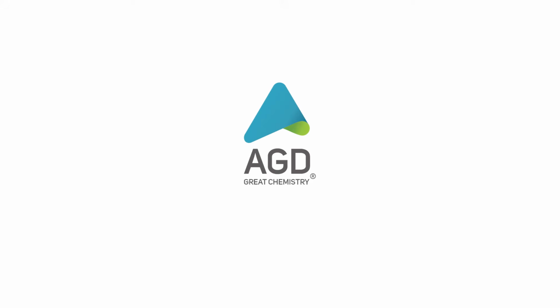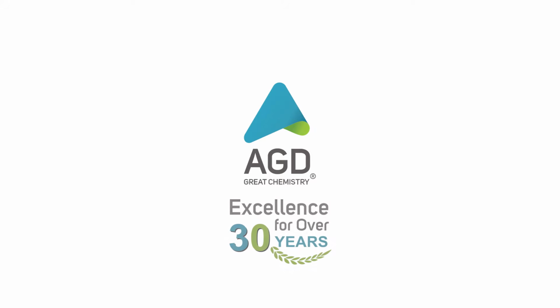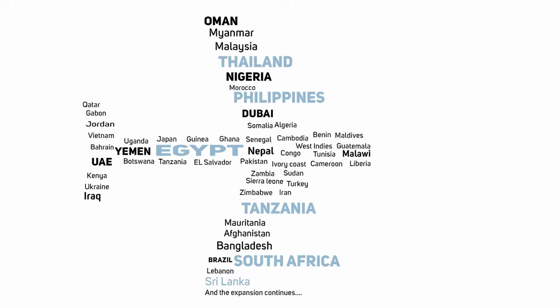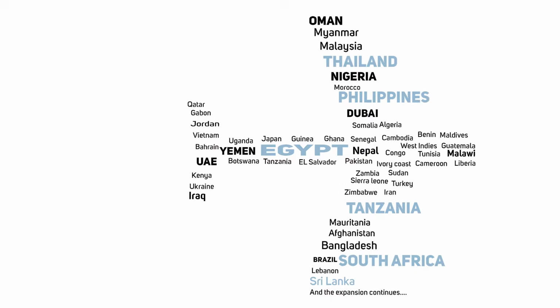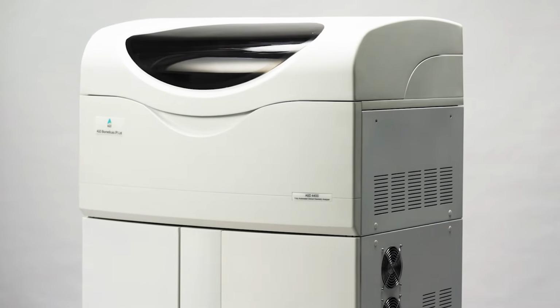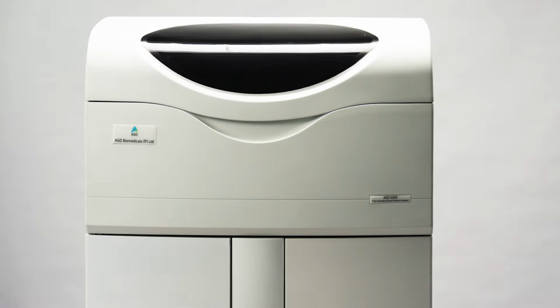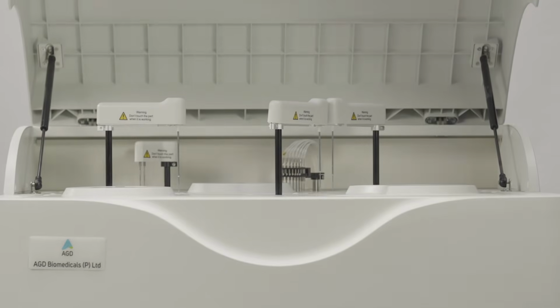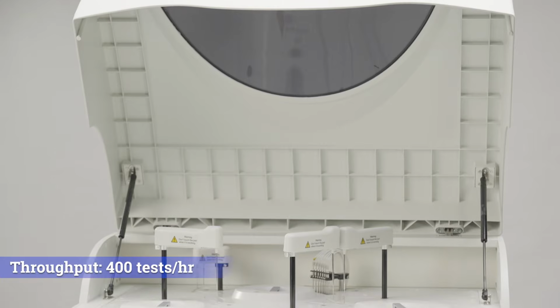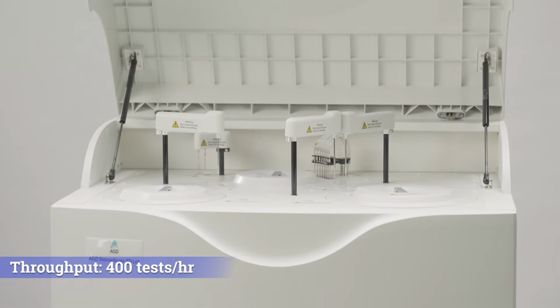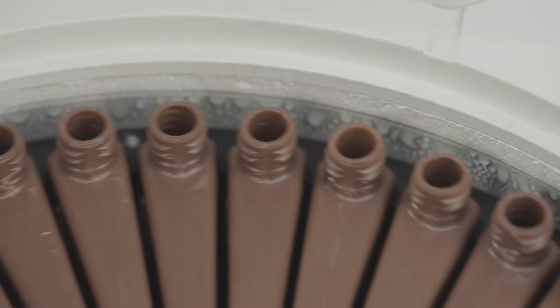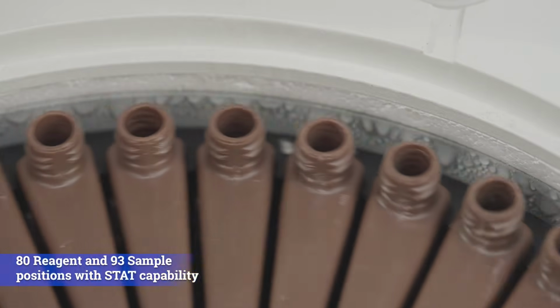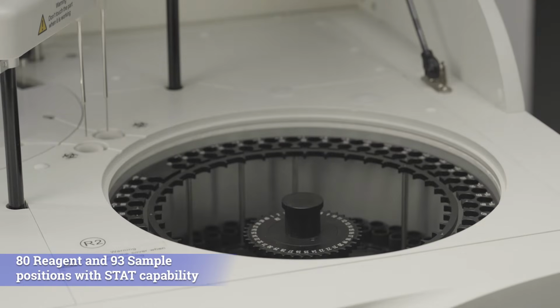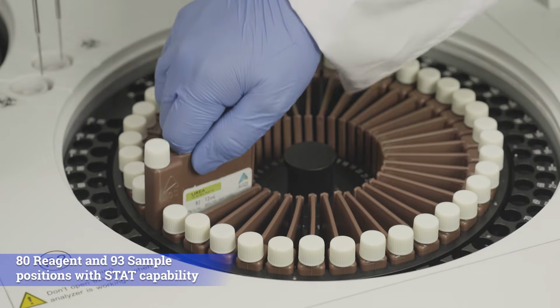AGD Biomedicals is known for researching, developing, and manufacturing biomedical equipment and reagents. Delivering excellent service globally, and defined by quality and precision, presents 4400. It is a compact floor model, fully automatic chemistry analyzer delivering 400 tests per hour for rapid analysis. With an advanced cooling system for 80 reagent positions and 93 sample positions with stat capability.